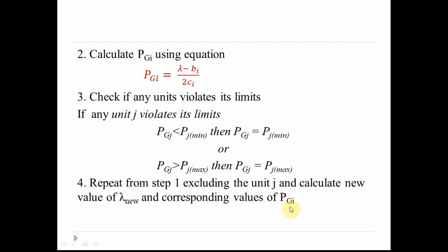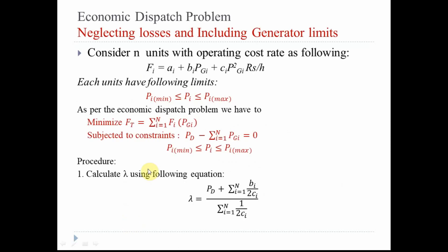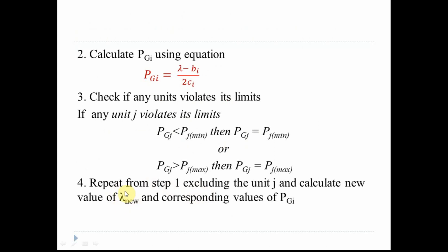The corresponding new values of PGI are then calculated for the remaining units. So starting with 4 units, when one unit is excluded due to limit violation and its value is fixed, the same lambda calculation procedure is repeated for the new reduced set of generating units. This new lambda is called the new lambda value.